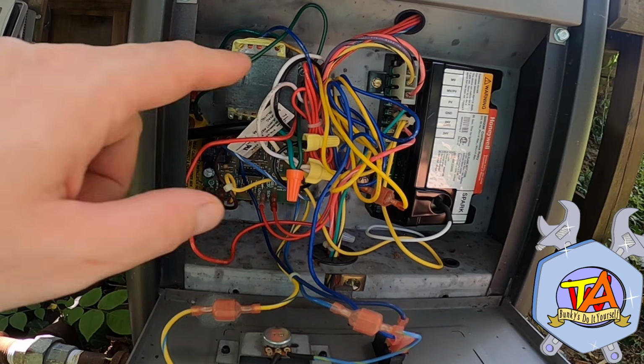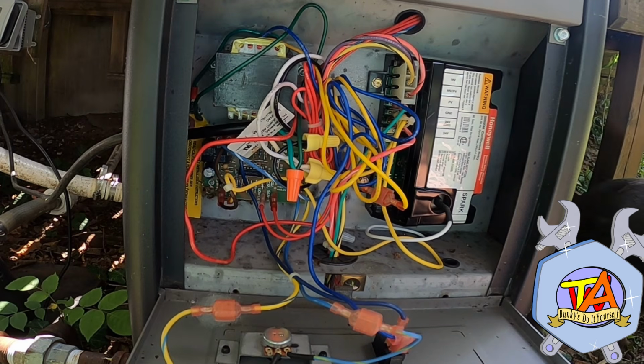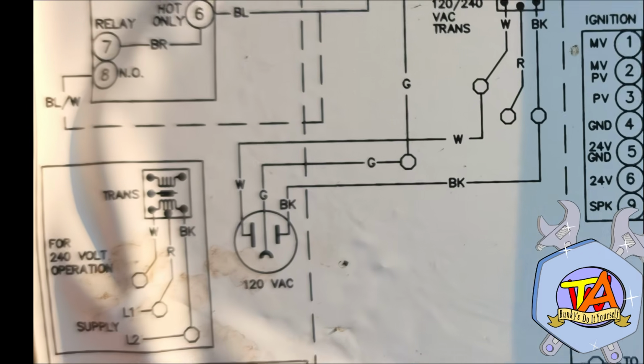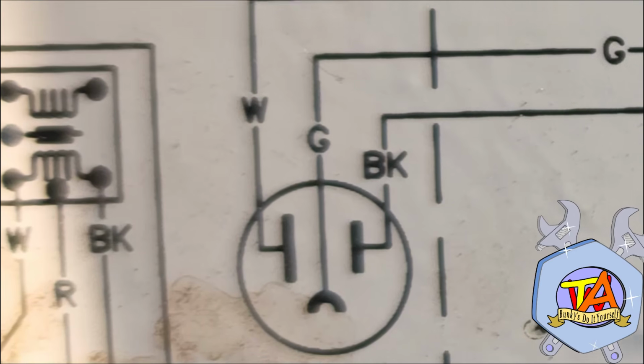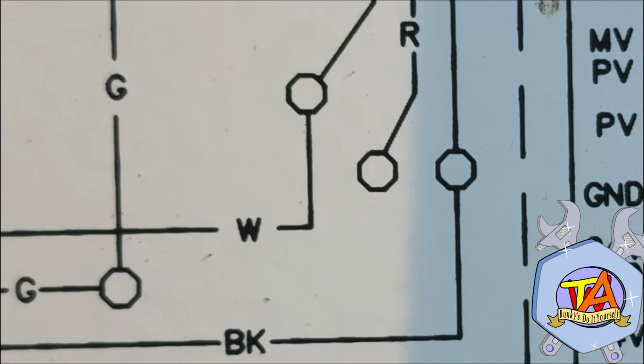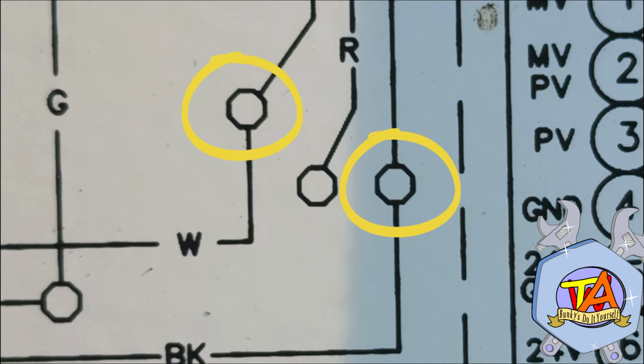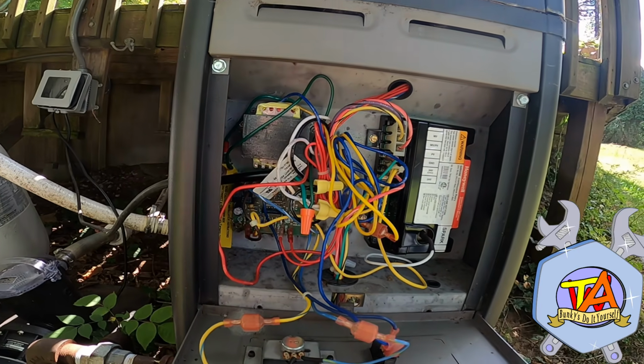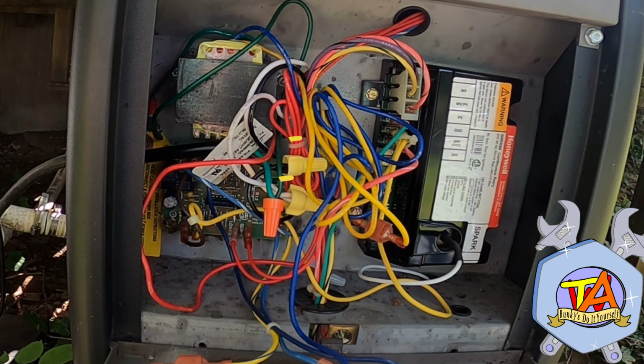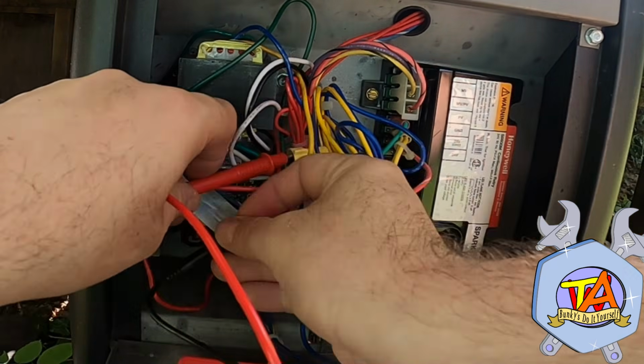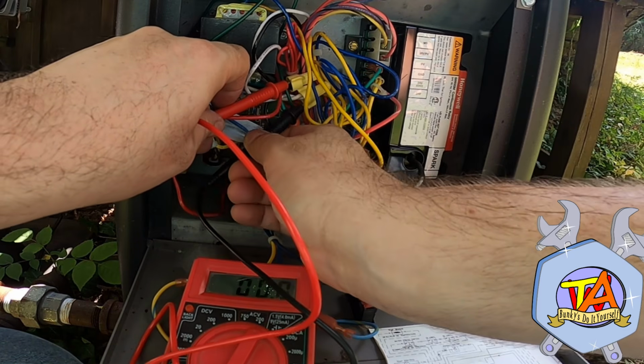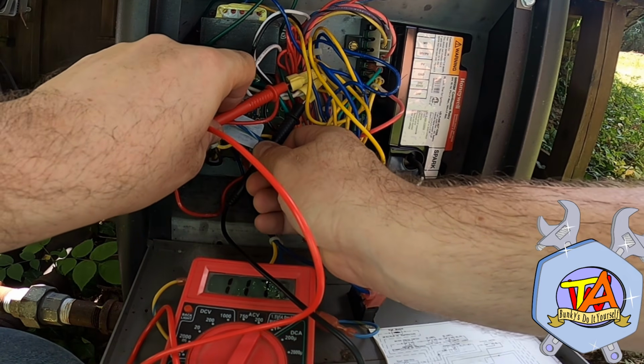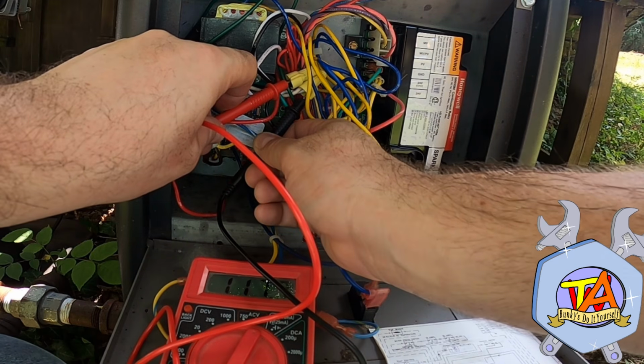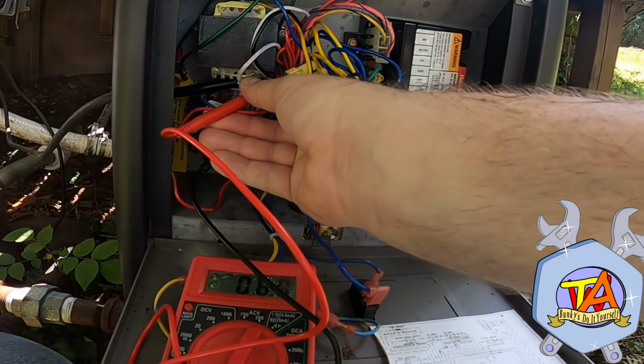First, let's check and see if there's power going into the unit. I've had to replace cords in the past. We know we have power to the outlet, as stated earlier. Now I follow the white and black wires. These 2 connector points will be a perfect spot where I can check and make sure that the cord is not burnt out. And here they are. Okay, let me see if I can get a reading off of them. As you can see, 117 AC volts. Should be anywhere between 110 and 120.